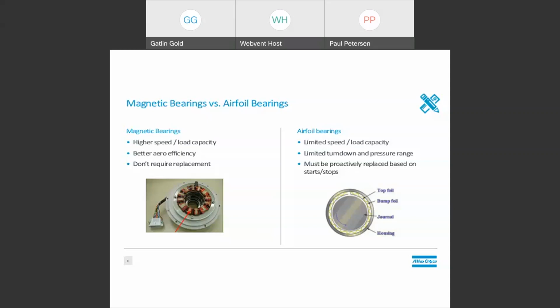The downside of this technology is it costs more than the airfoil. However, what differentiates Atlas Copco in this regard is our backup bearing. Atlas Copco uses a ceramic backup bearing that allows up to 5 full-speed crashes before they need to be replaced. With over 600 magnetic bearing turbos in operation, some for upwards of 18 years, Atlas Copco has never had to replace a set of bearings or backup bearings in our turbo blowers.